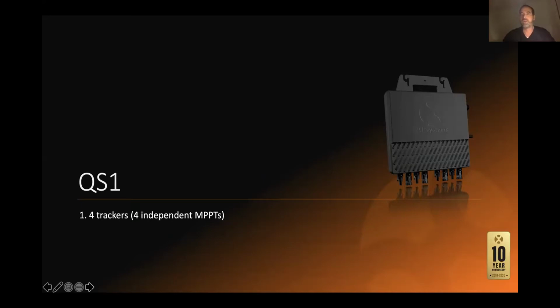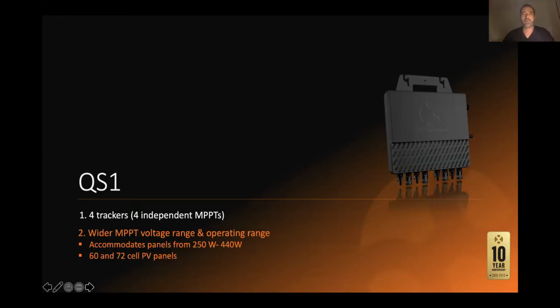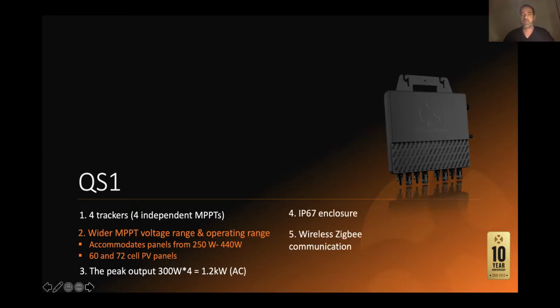For MPPT, every 4 modules connected to the QS1 will work independently. You can use modules of different type, brand, or orientation - east, west, no problem. Same as the YC600, only 60 and 72 cell panels, same wattage range. Basic calculation: 1200 watt AC, ratio of 1.2, so you can push to 1400 watt on the DC side, and if you push further the micro still won't be damaged - maybe a little peak shaving around noon in summer. IP67, Zigbee, single phase, but again you can build it into 3 phase and balance the phases during installation.